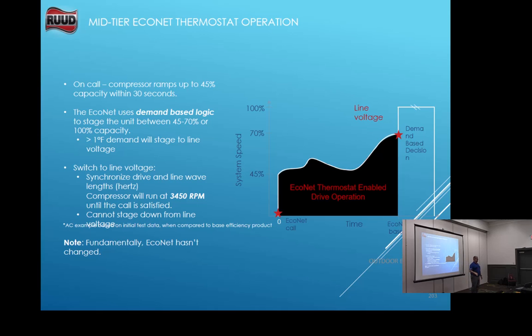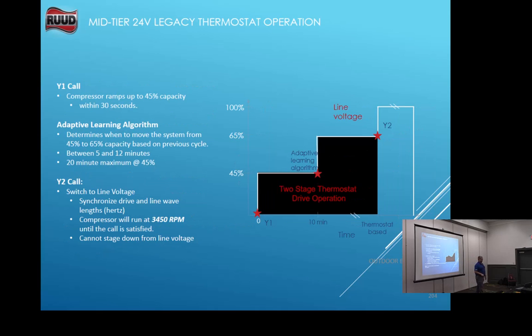Now, we talked about that 3-speed, 2-stage stat a while ago. If you're putting it on a regular 24-volt legacy thermostat, just like what's over there on the wall, the compressor ramps up to 45% within 30 seconds. First speed.